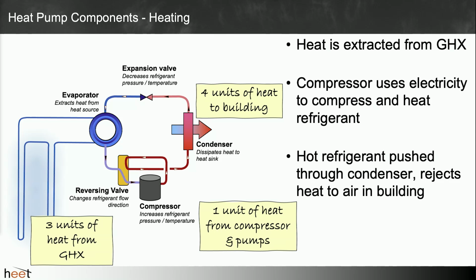And this is how you get your coefficient of performance. So you may have heard the word COP or coefficient of performance, and this is how it works. You transfer those 4 units of energy, which is combined thermal and electrical energy, to the space by only paying for 1 unit of electrical energy to power that compressor, circulation pump, and fans.